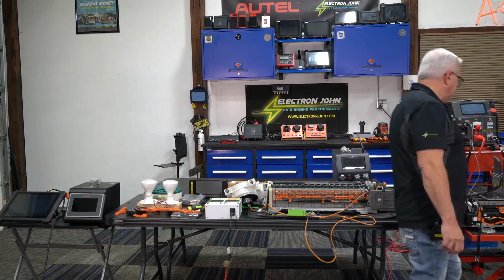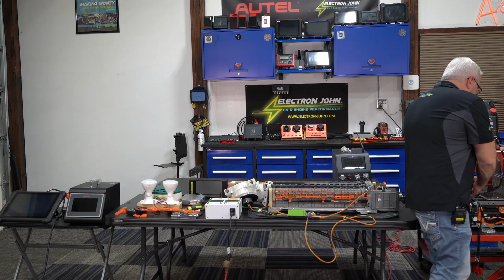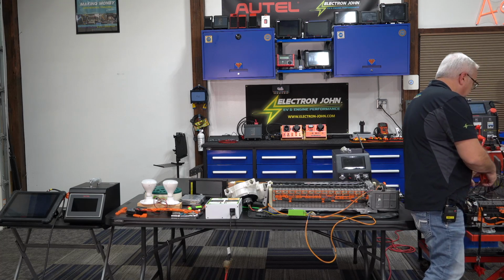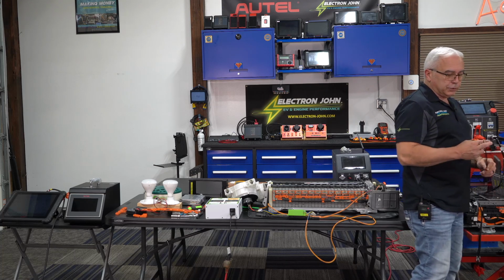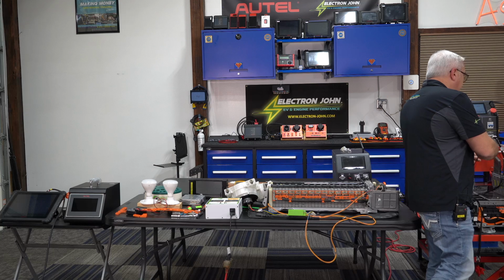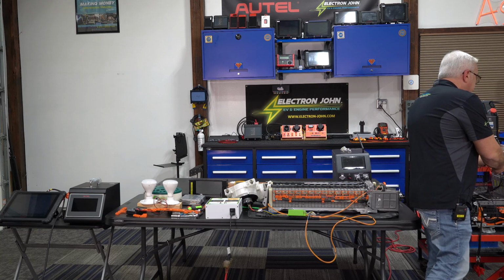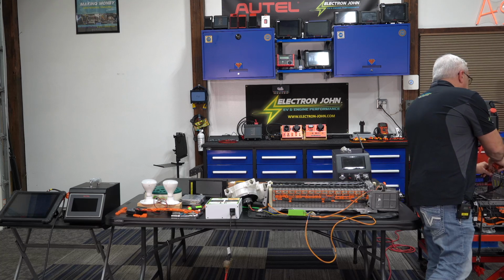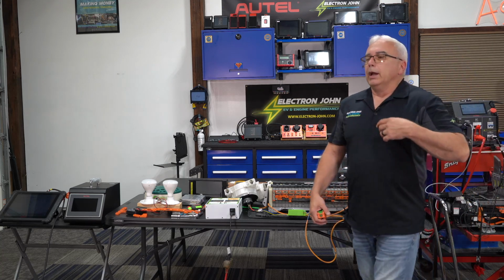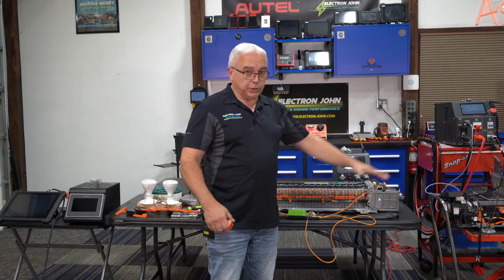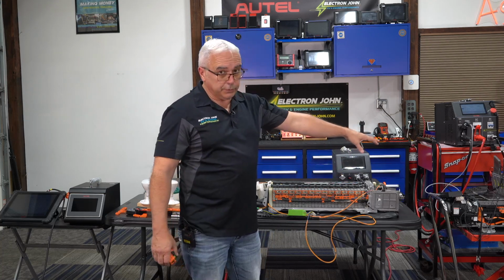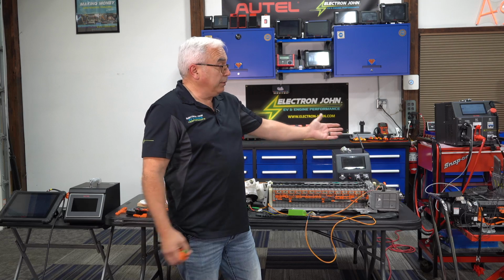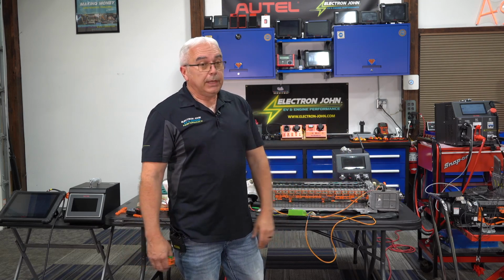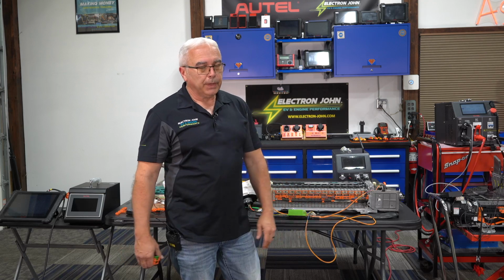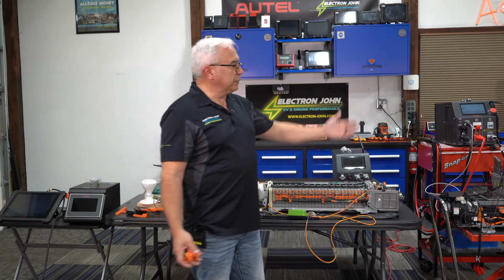Now one thing I want to throw out there as a word of caution is we also have these extra wires on our string module, and we've said this in the other videos. These are our temperature wires. So I want to make sure before I start a process that I have these strategically placed around the battery cells. Here's the reason being. The tool is assuming you've set it up correctly. So if that one module fully charges to about 36 volts on average for this particular battery pack, if I told it that it was, let's say, 136 volts, it's going to try to charge it to 136 volts. It will not be able to shut itself off if there's no safety built into it.